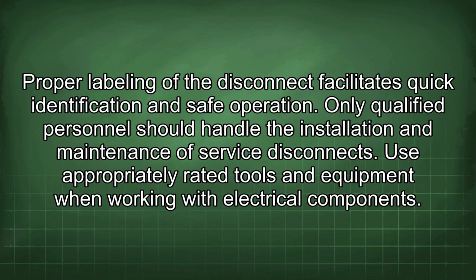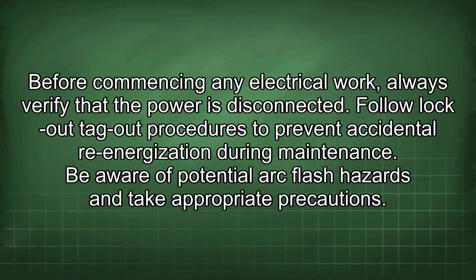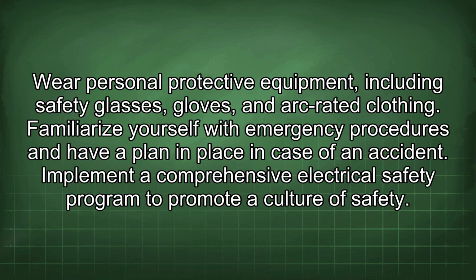Proper labeling of the disconnect facilitates quick identification and safe operation. Only qualified personnel should handle the installation and maintenance of service disconnects. Use appropriately rated tools and equipment when working with electrical components. Before commencing any electrical work, always verify that the power is disconnected. Follow lockout tag-out procedures to prevent accidental re-energization during maintenance. Be aware of potential arc flash hazards and take appropriate precautions. Wear personal protective equipment, including safety glasses, gloves, and arc-rated clothing.